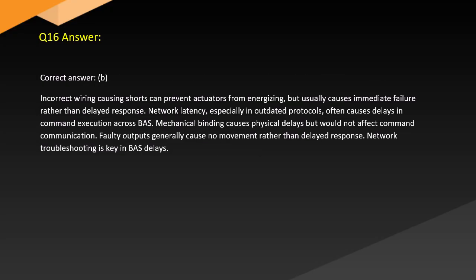Answer. Correct answer: B. Incorrect wiring causing shorts can prevent actuators from energizing, but usually causes immediate failure rather than delayed response. Network latency, especially in outdated protocols, often causes delays in command execution across BAS. Mechanical binding causes physical delays, but would not affect command communication. Faulty outputs generally cause no movement rather than delayed response. Network troubleshooting is key for BAS delays.